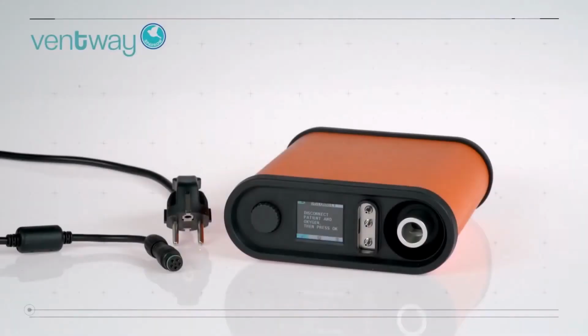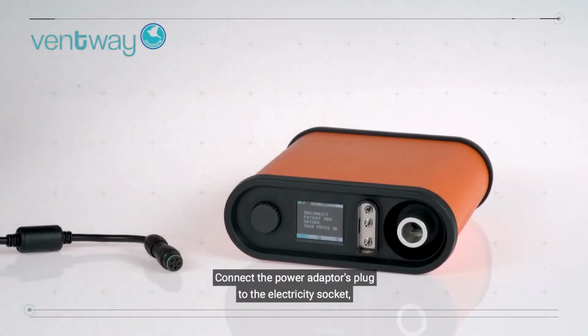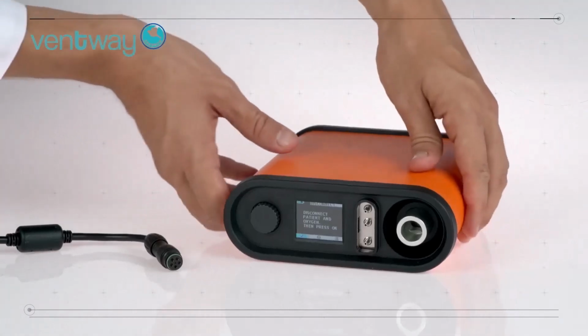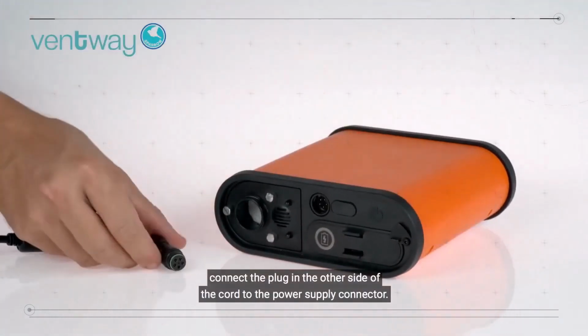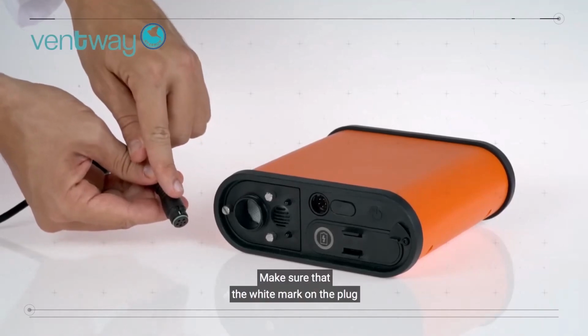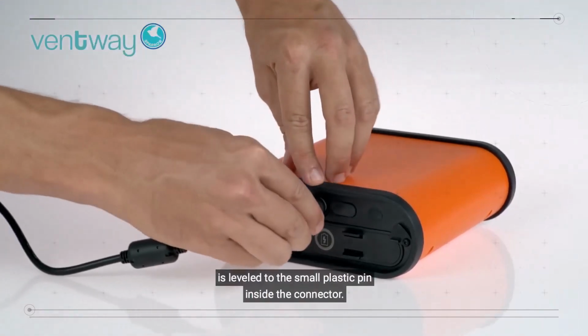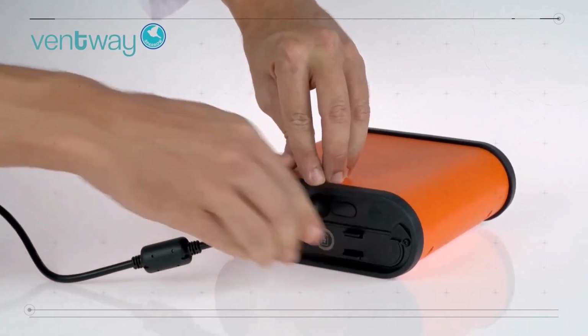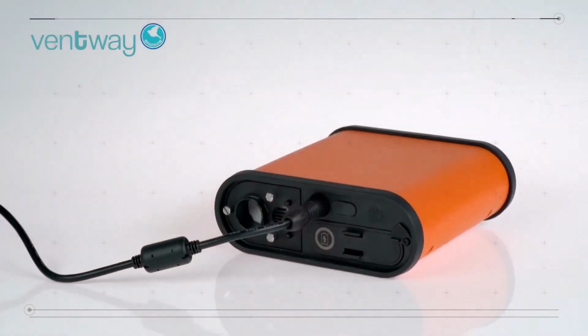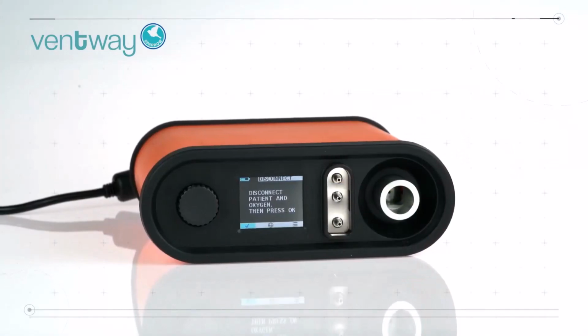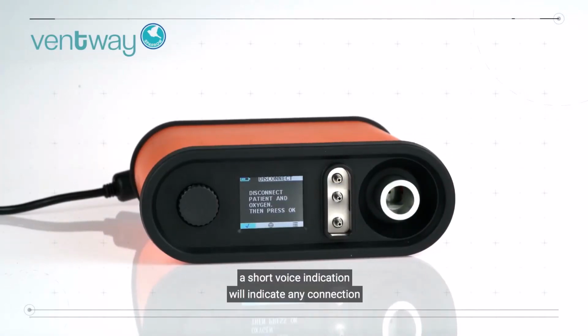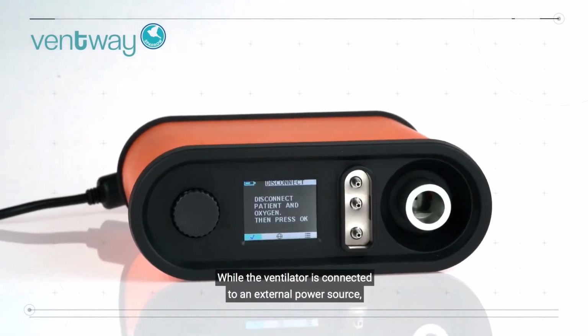External connections. Connecting AC power. Connect the power adapter's plug to the electricity socket. Connect the plug in the other side of the cord to the power supply connector. Make sure that the white mark on the plug is leveled to the small plastic pin inside the connector. In case the ventilator is turned on, a short voice indication will indicate any connection or disconnection of the power adapter. While the ventilator is connected to an external power source, it will automatically charge a rechargeable battery.